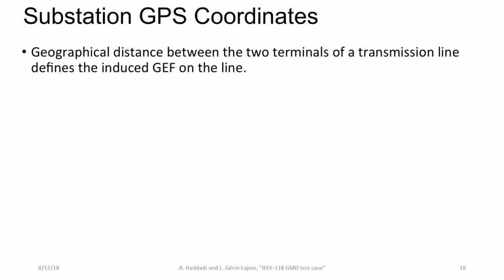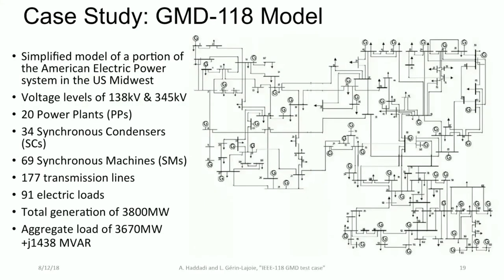We have developed a test case called GMD-118. It includes all these modeling details: nonlinear transmission line models, nonlinear transformer models with actual measured characteristics, generator models including control and protection for specialized studies, harmonic measurement devices placed everywhere, and the geo-electric field representation. Some results: this is the simulation of the NERC benchmark GMD event.